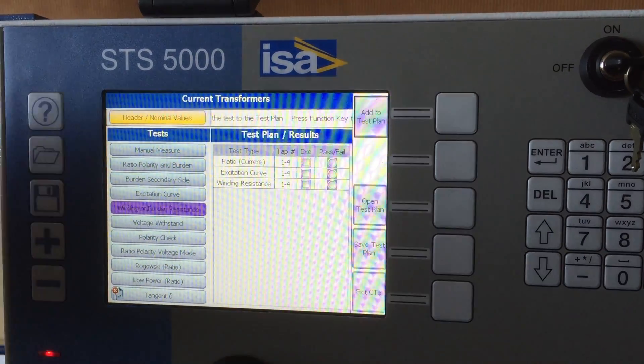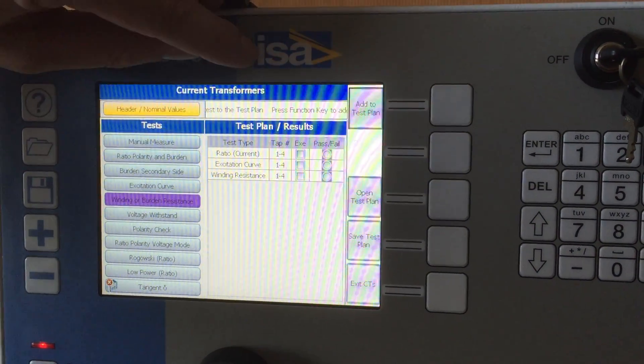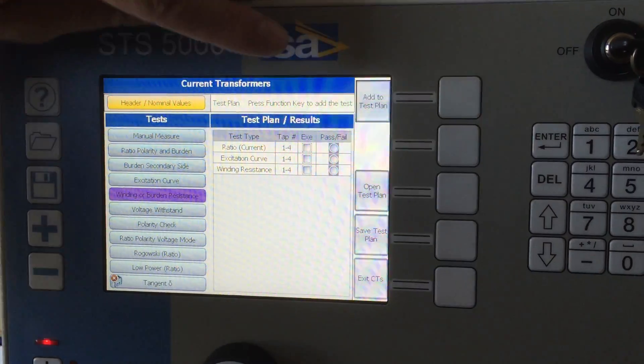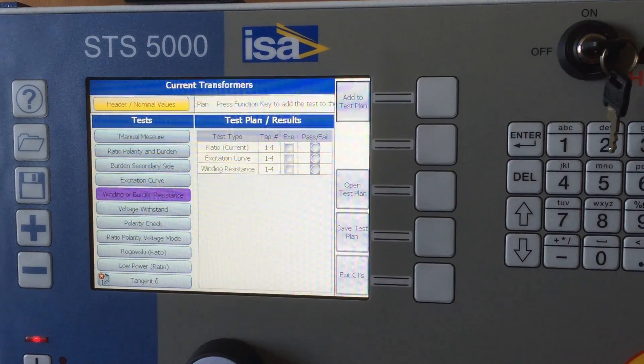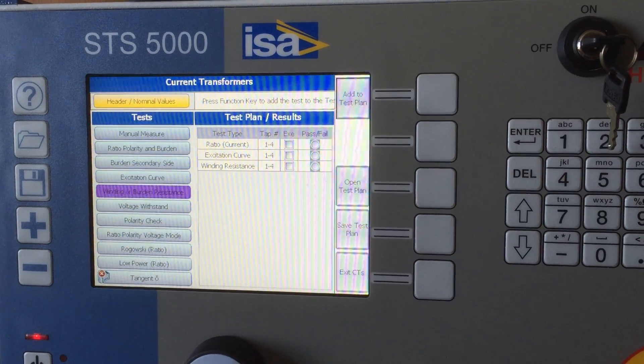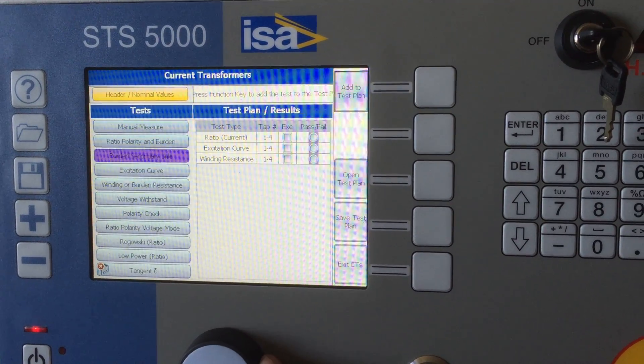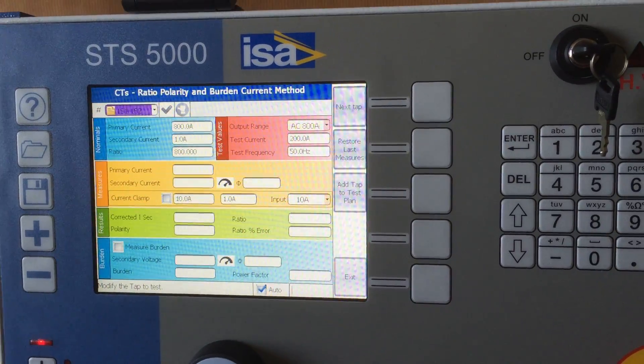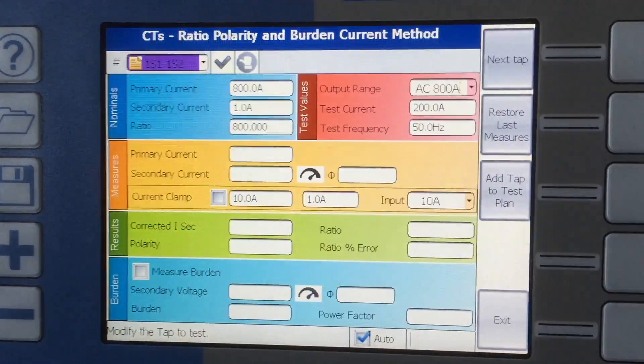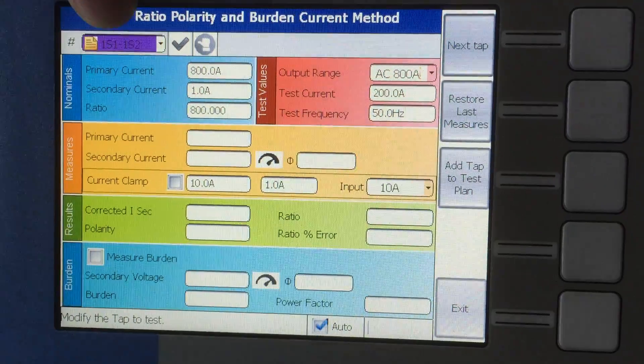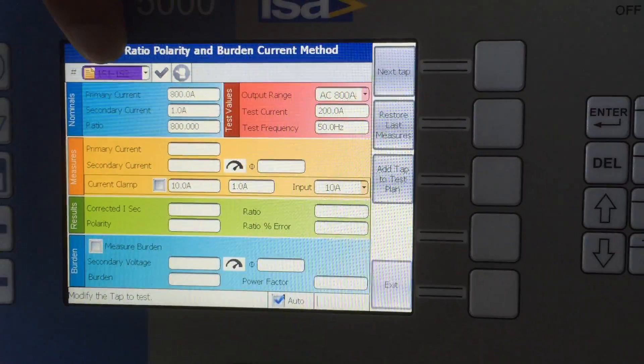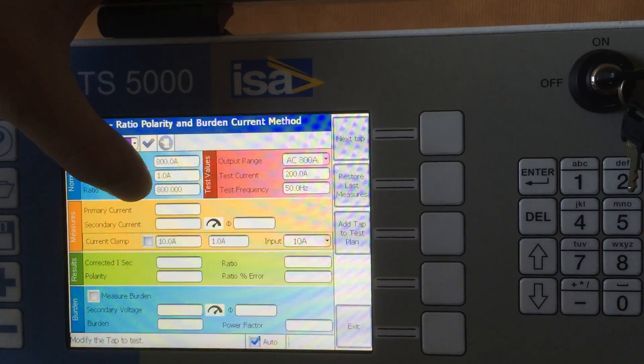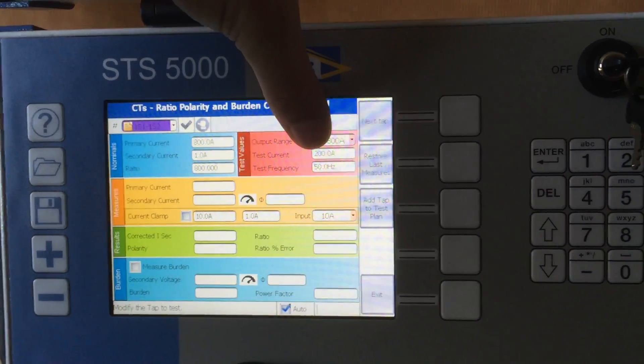At the end, you will get a tick here because it will be executed, and a red, yellow, or green color in the pass or fail column. Now, if I wanted to do a single test, we'll take two examples for a CT. One of them is ratio, polarity, and burden. It would look like this. Since it read from before that my tap one is 800 to 1, the nominal ratio is 800.